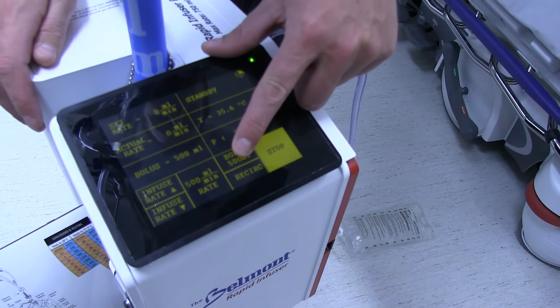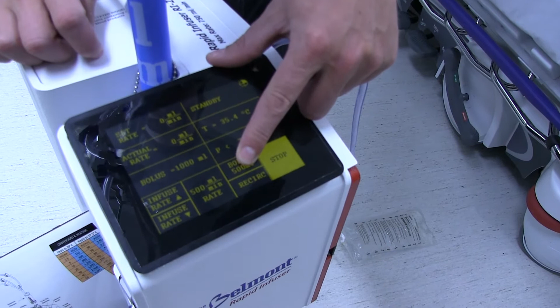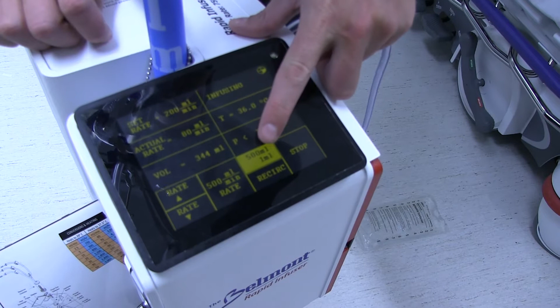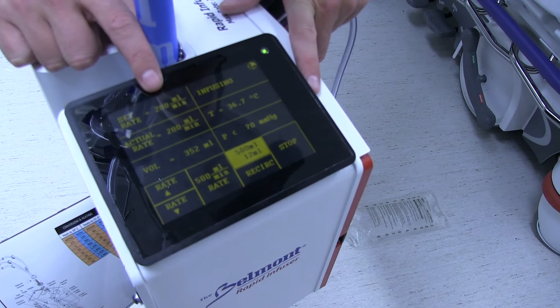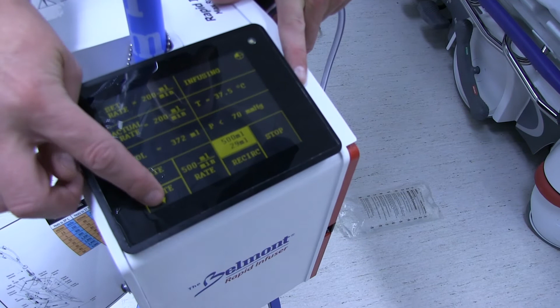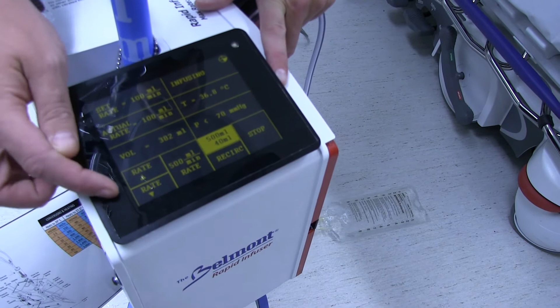You can give continuous infusion, but you can also give boluses. So hold the key, and you can choose different volumes: 100, 200, 400, 500, or a liter. It's just on a loop, so you can just find your number when you see it again. Let's say 500. No matter what volume you choose, the rate for the bolus is going to try to work its way to 200 a minute. Now, if the catheter allows it, great. If not, you may have to adjust. Say, okay, I want to do 500 over 5 minutes. Bring the rate down to 100 a minute. So you can adjust the rate however you like for the bolus as well.